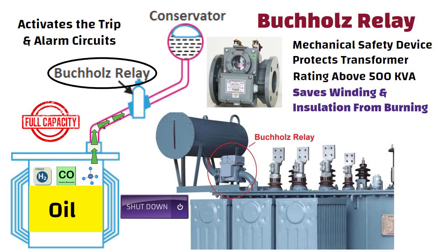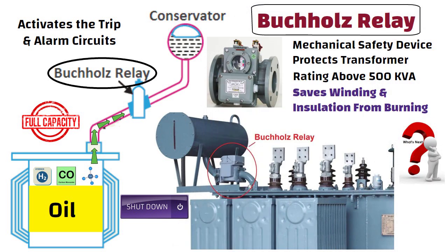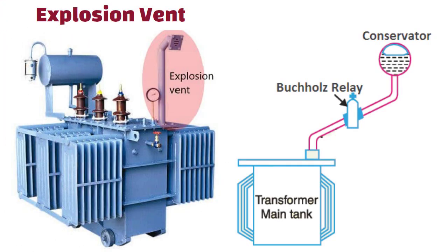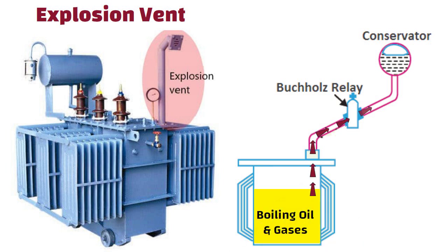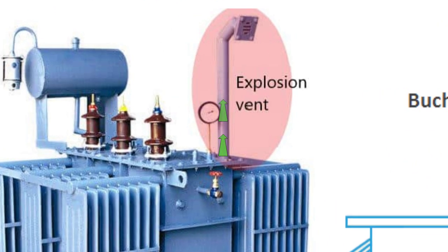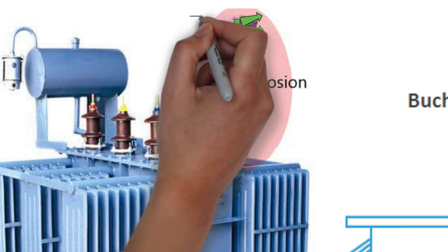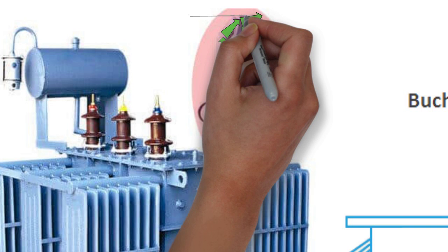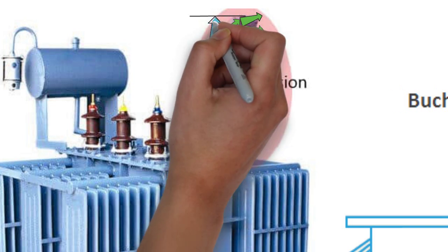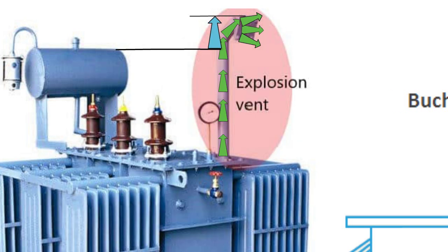Suppose by any chance the Buchholz relay stops functioning, then what happens? That's why one more safety device is installed in the transformer, called the explosion vent. When boiling oil and gases in the transformer come up to the conservator tank, they come out of the explosion vent to avoid explosion of the transformer. You can see here, the level of the explosion vent is normally maintained above the level of the conservator tank.